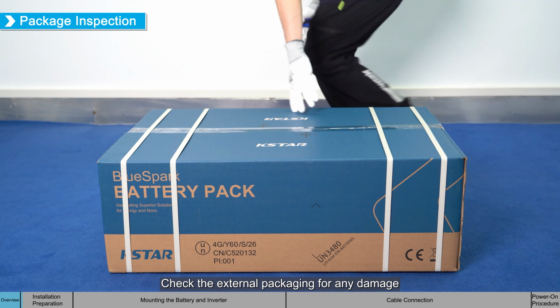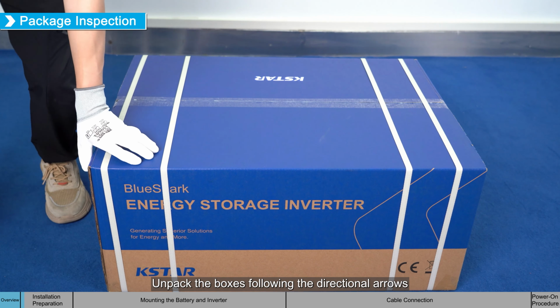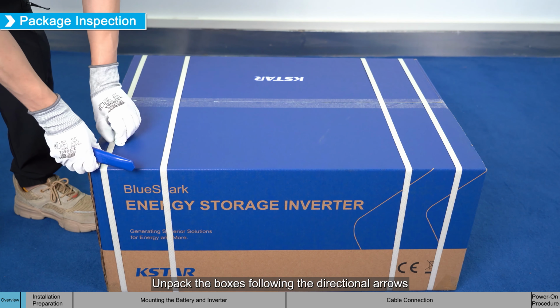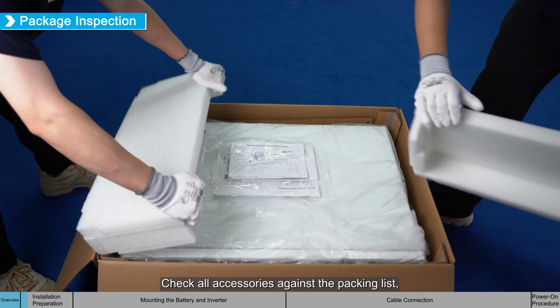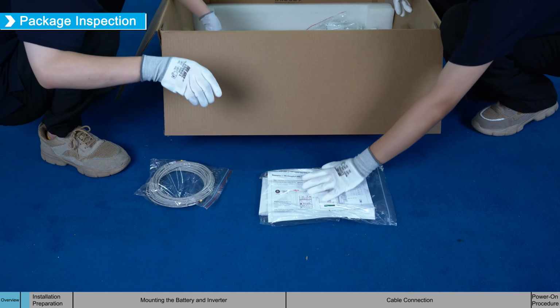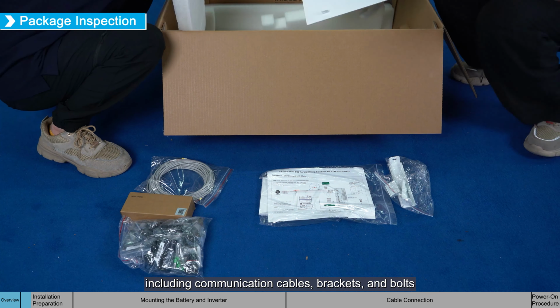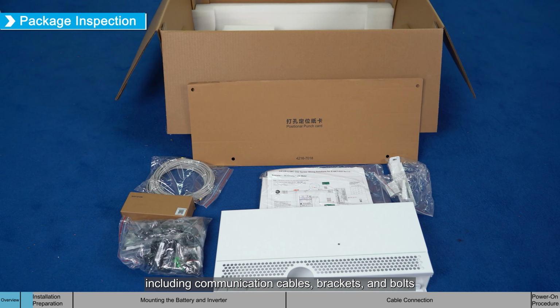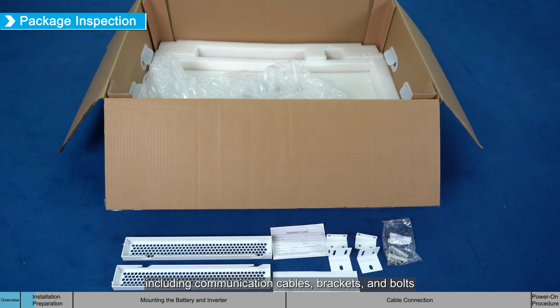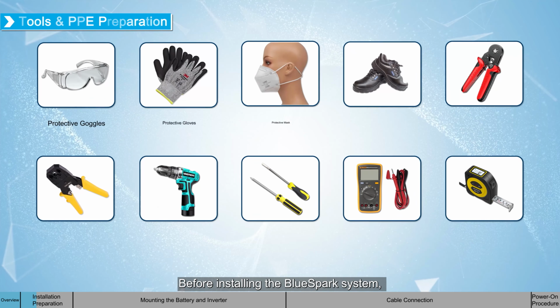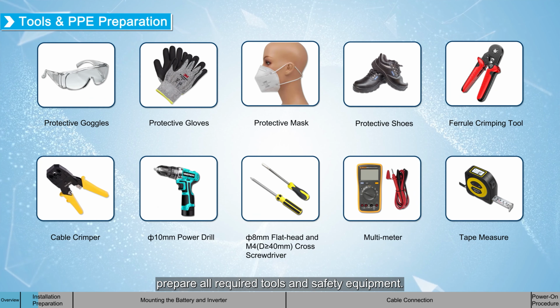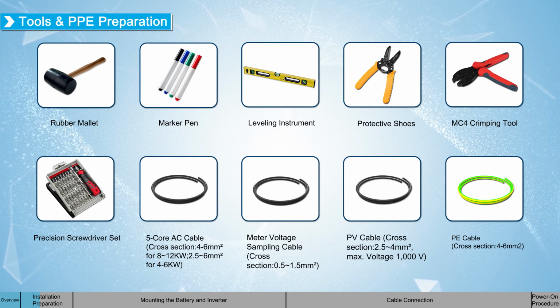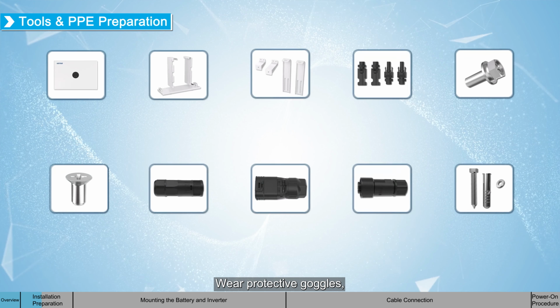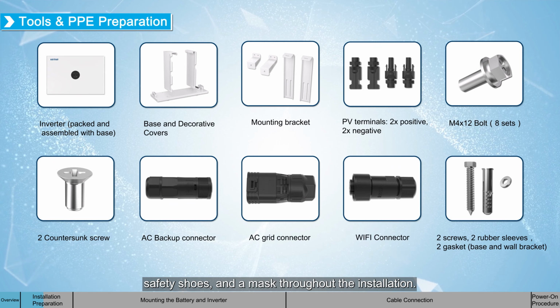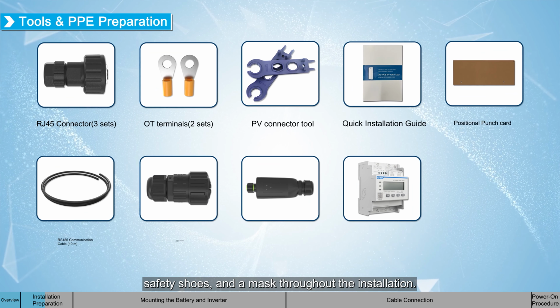Before installation, inspect all packages carefully. Check the external packaging for any damage. Unpack the boxes following the directional arrows. Check all accessories against the packing list, including communication cables, brackets, and bolts. Before installing the BlueSpark system, prepare all required tools and safety equipment. Safety first. Wear protective goggles, insulated gloves, safety shoes and a mask throughout the installation.